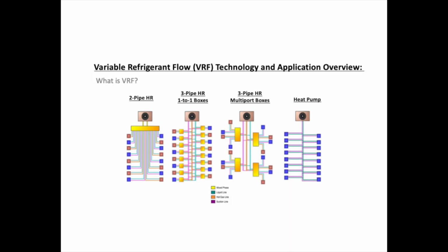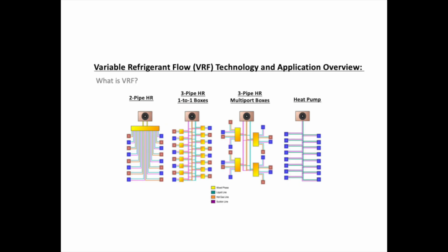And here's an overview of the different piping schematics for our different systems. You have your simple two-pipe heat recovery. We have our three-pipe heat recovery with one-to-one flow selector boxes. We have our three-pipe heat recovery with multi-port distribution boxes. And we have our simple two-pipe heat pump system. And here you can see the different color coding of the different refrigerant pipes. You have your mixed phase, you have your hot gas, you have your suction, and you have your liquid line.